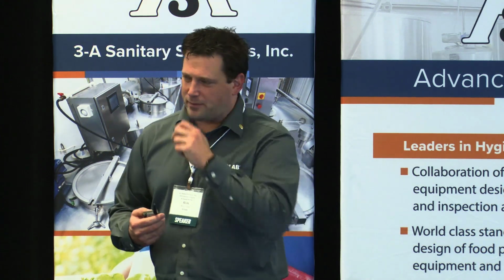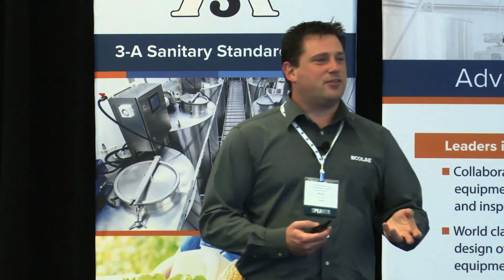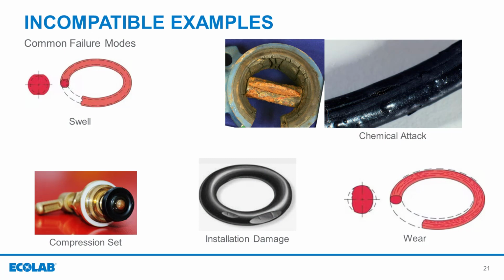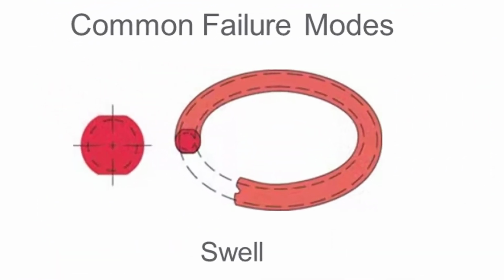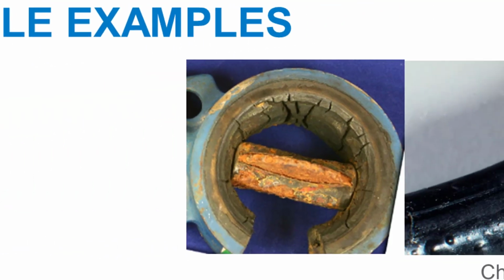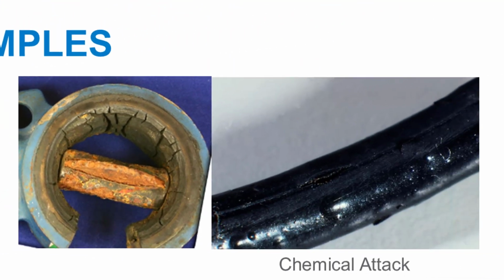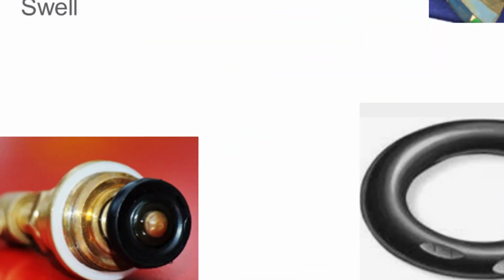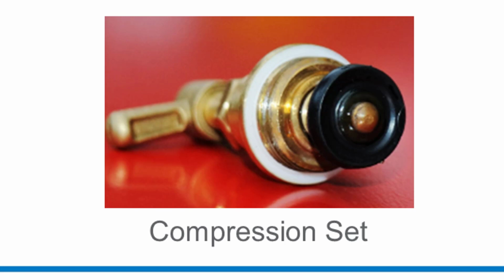Here's my last slide about pictures. I just wanted to give you an example of what you're looking for visually. If it expands, it's not going to fit. It could cause some issues. Cracking is obvious. Chemicals on the right will give you that oily substance or that compression set. This is a really good one because a lot of people can relate. You close off a faucet, and after you close it off enough, it starts to leak. That's because of compression set.